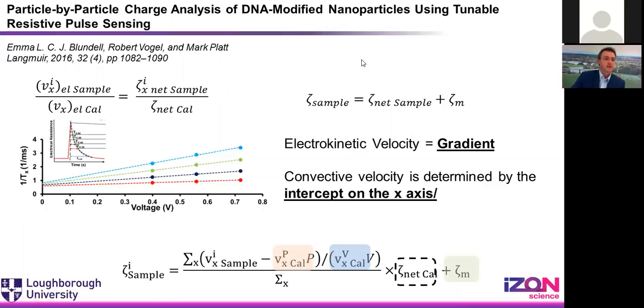It says that the sample zeta potential is equal to the velocity of the sample that I've measured, and I'm just going to get my annotation tool. So here's my zeta potential of the sample. I've got a measured velocity of a sample. The zeta potential of the sample that I'm interested in can be found out by measuring the velocity of the sample, subtracting, if you like, the contribution from the convective velocity, divided by the velocity of the particle, the electrokinetic velocity, times the net zeta potential of the calibrant plus this contributing factor from the pore wall.